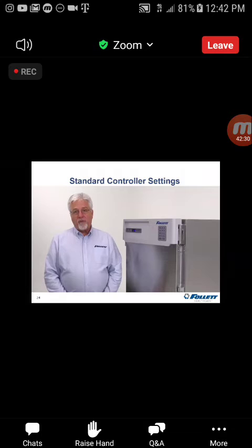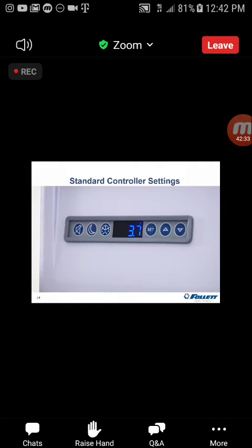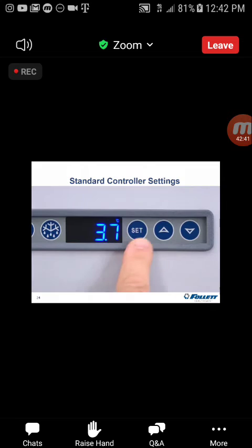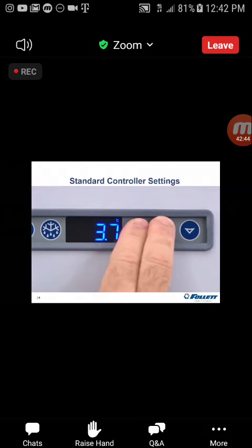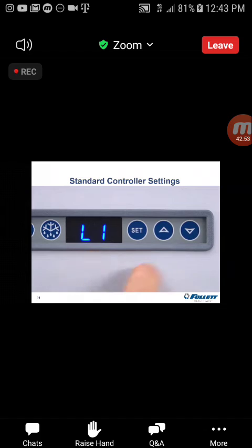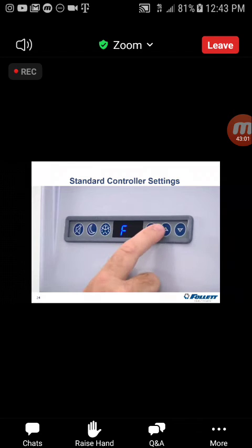Follett refrigerators and freezers come factory programmed in degrees Celsius. If degrees Fahrenheit is preferred, that can be changed by entering the first level of hidden menu. Press and hold the set button and the arrow closest to it, which is the up arrow. Wait a few seconds, and then L1 will appear in the display. While L1 is in the display, scroll until UNT appears in the display. Press set, and the display will indicate C. Then use the up or the down arrow to change the C to F and hit set to accept the new setting. The display has now been switched to degrees Fahrenheit.